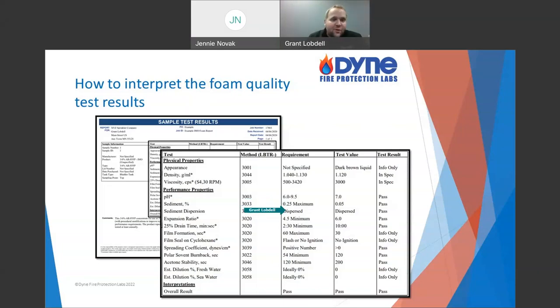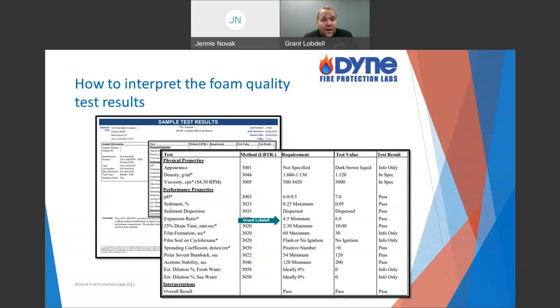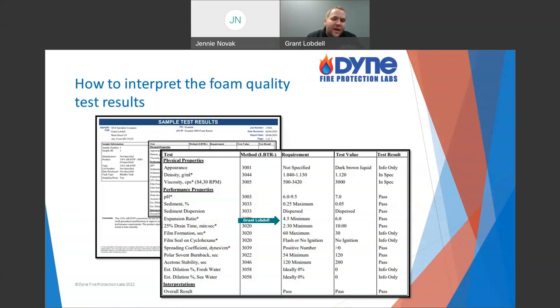For expansion and drain time performance properties: why would expansion be low? Dilution, and age is a big factor. These foams aren't designed to last forever. Some last a long time — especially older ones that are full of C8, full of PFAS. That PFAS molecule is designed to last, which is why we're in the problem we're in now. Age and storage conditions are very important for all performance properties — especially heat and direct sunlight, which provide energy for reactions, things breaking down, things baking off. Generally, expansion ratio only ever goes down from where it started; a product is not going to improve as it sits in the field.